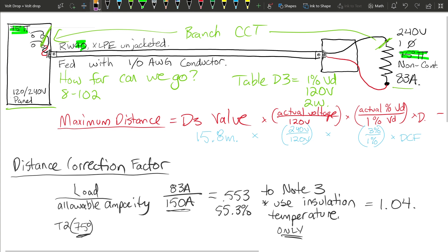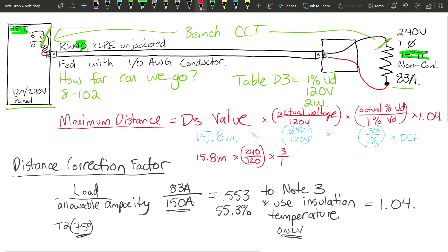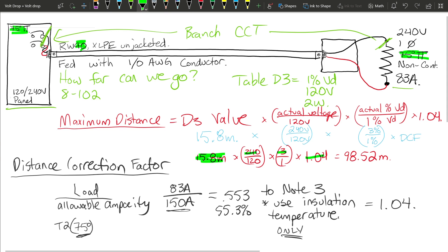We plug 1.04 in as our DCF. So the full calculation is: 15.8 meters × (240/120) × (3/1) × 1.04, which gives us approximately 98.52 meters. If this had been a straightforward 120 volt circuit at 1% volt drop, we would have been limited to 15.8 meters. But because we're at 240 volts, 3% volt drop, and we gained a little extra from the distance correction factor, the maximum distance is 98.52 meters.